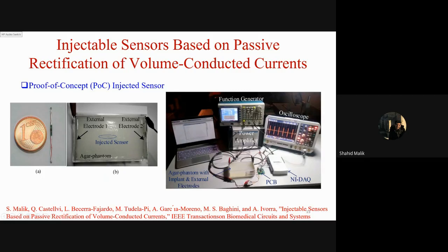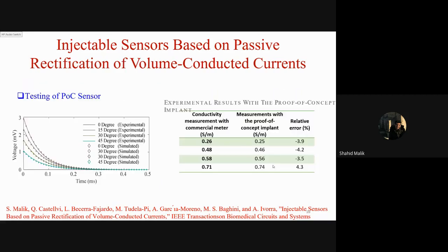Here we can see the whole setup. These are function generators which provide the burst signal. This is a power amplifier, because we need a relatively higher amplitude to power the capacitor in the injectable sensor. And then this circuitry is connected to an NI DAQ card, which has an ADC with a very high resolution of 16-bit. So this is the setup that we have used, and again we have tested it for multiple conductivities, and we are able to measure the conductivity of the tissue wirelessly. So this proved the novelty of the approach, that it can be used for power transfer as well as sensing.